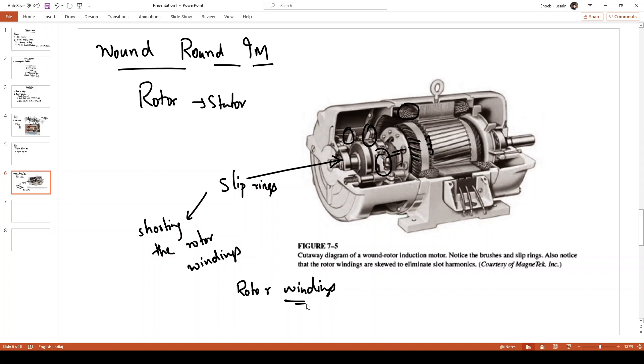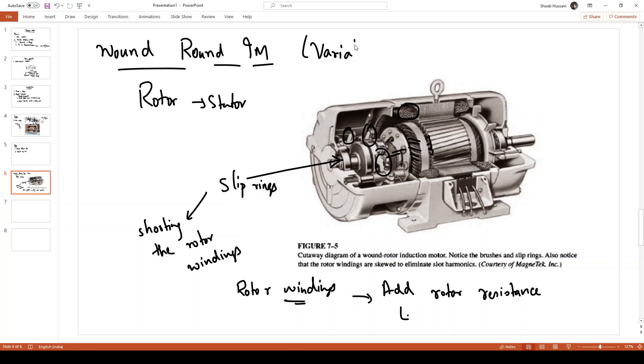In the wound rotor induction motor, the rotor windings are connected to a slip ring arrangement, and we can add additional external rotor resistance to this circuit. The rotor resistances or rotor windings are accessible through the slip rings, so by means of these slip rings we can add additional resistance to the rotor windings. This is primarily done for speed control. Therefore, the wound rotor induction motor is also known as the variable speed induction motor.